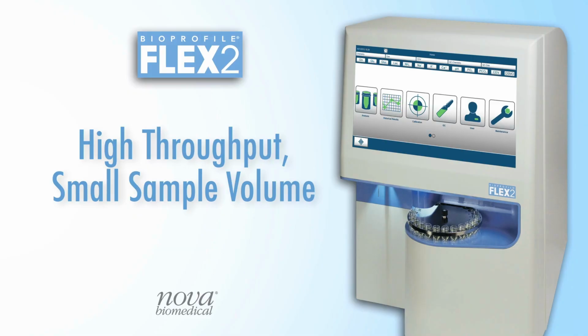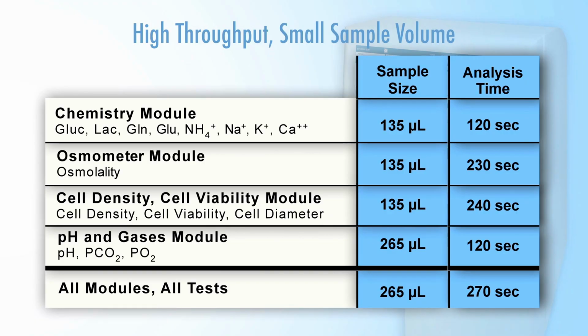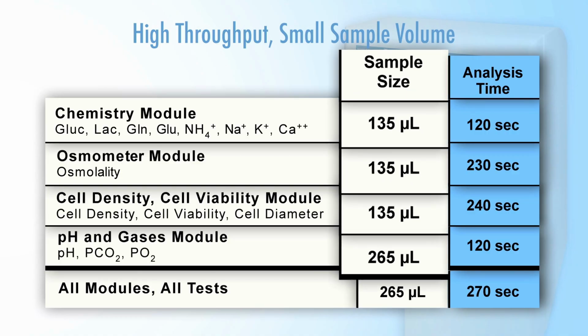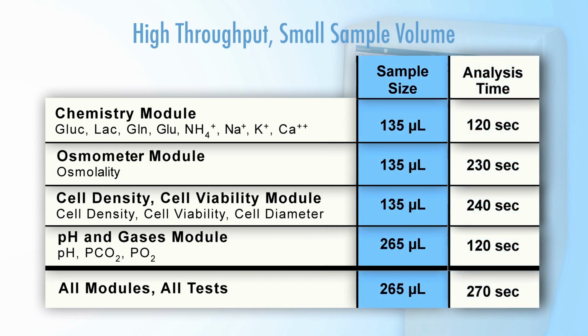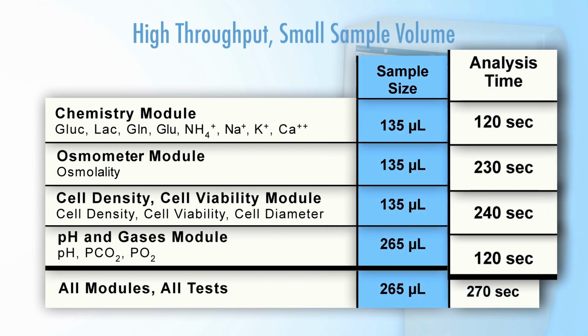With high-throughput testing and small-volume culture systems in mind, FLEX 2 has been designed to provide a full panel of tests very rapidly, with small sample volume. Most tests can be done with just 135 microliters of sample, while a full panel of analyses can be achieved with just 265 microliters. FLEX 2 test times have been reduced by 50%.